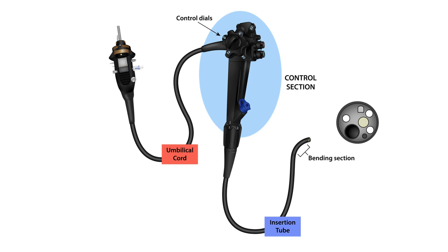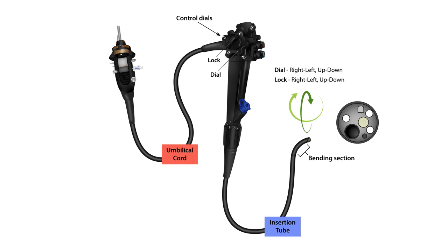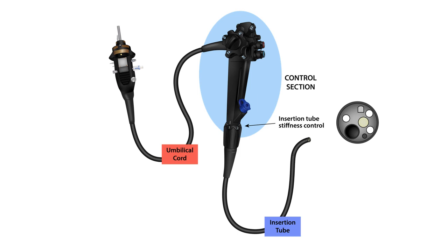So this is accomplished by moving the control dials. The control dials allow the endoscope bending section to move either to the right or to the left, up or down, and in addition there are locks to keep the bending section in a particular direction. Sometimes the colon could be loopy, and you could stiffen the scope by tightening the stiffness control.